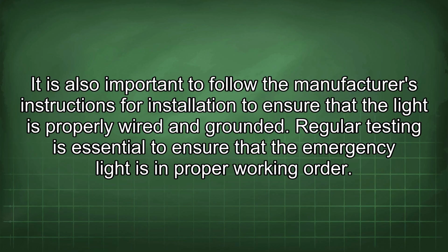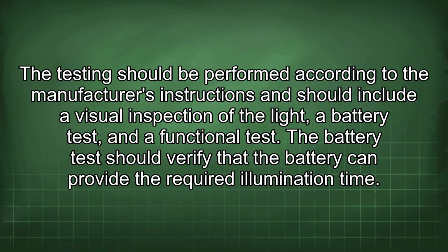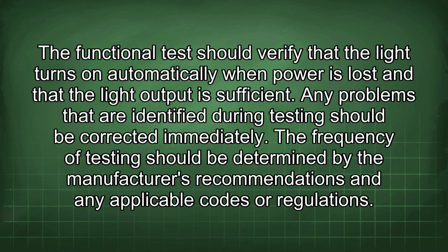Regular testing is essential to ensure that the emergency light is in proper working order. The testing should be performed according to the manufacturer's instructions and should include a visual inspection of the light, a battery test, and a functional test. The battery test should verify that the battery can provide the required illumination time. The functional test should verify that the light turns on automatically when power is lost and that the light output is sufficient. Any problems that are identified during testing should be corrected immediately.